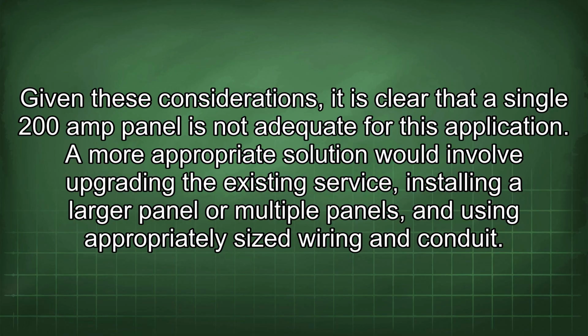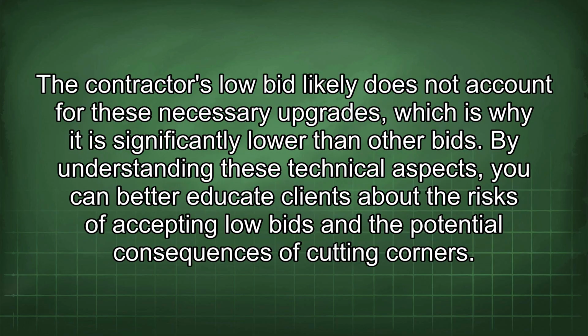A more appropriate solution would involve upgrading the existing service, installing a larger panel or multiple panels, and using appropriately sized wiring and conduit. The contractor's low bid likely does not account for these necessary upgrades, which is why it is significantly lower than other bids.